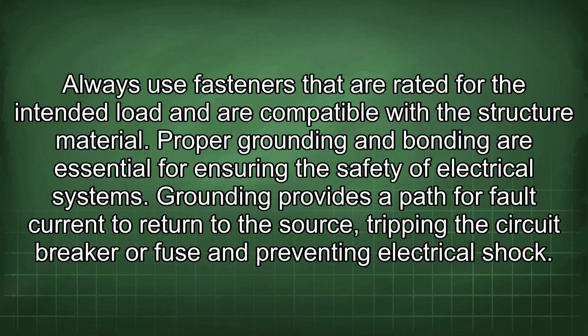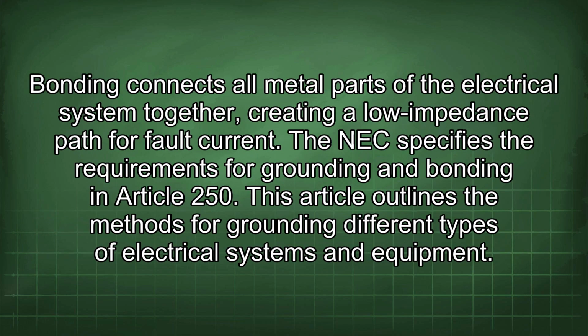Proper grounding and bonding are essential for ensuring the safety of electrical systems. Grounding provides a path for fault current to return to the source, tripping the circuit breaker or fuse and preventing electrical shock. Bonding connects all metal parts of the electrical system together, creating a low impedance path for fault current. The NEC specifies the requirements for grounding and bonding in Article 250. This article outlines the methods for grounding different types of electrical systems and equipment.